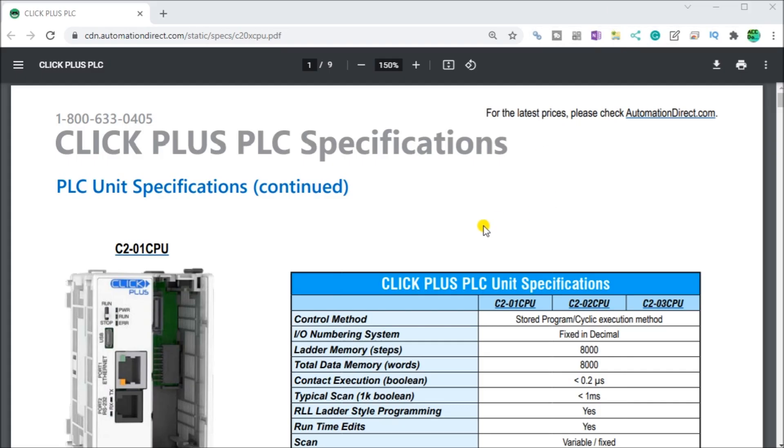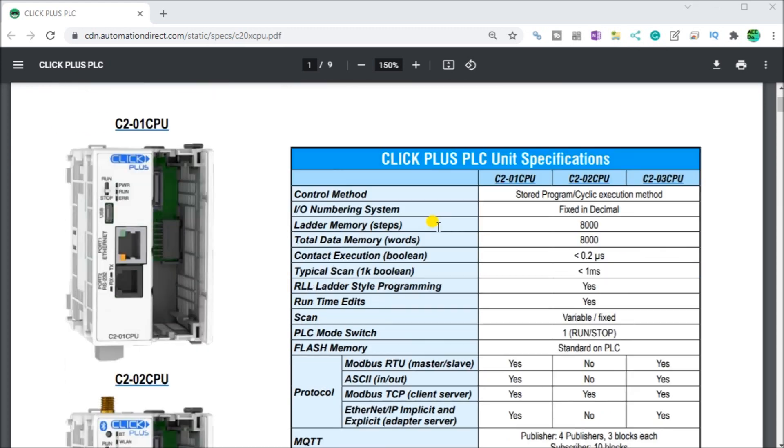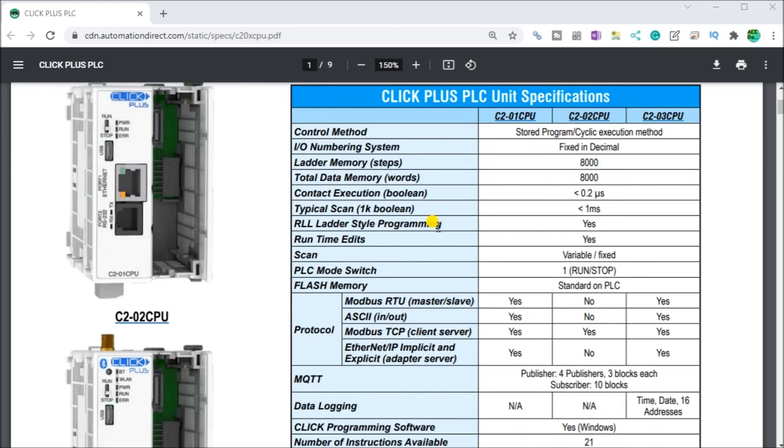Calling up the specifications for the Click Plus PLC, you can see that we have flash memory standard on the PLC. So I know that my PLC program itself is stored in this flash memory which will be non-volatile so it'll automatically be saved when I lose power. So my battery in the Click does not support the program itself, it's used for data memory and I/O.